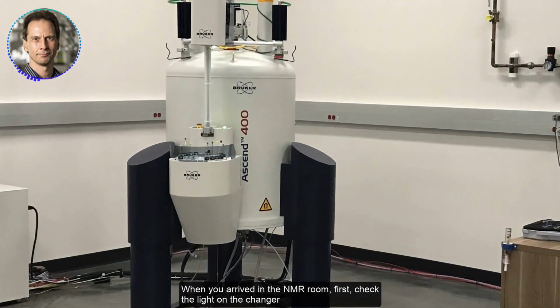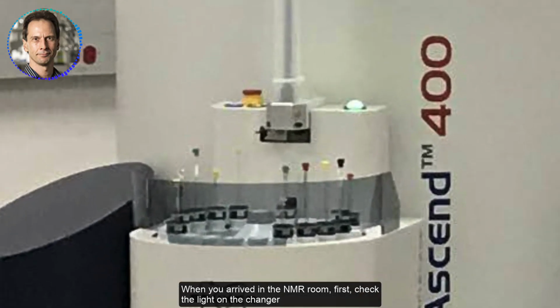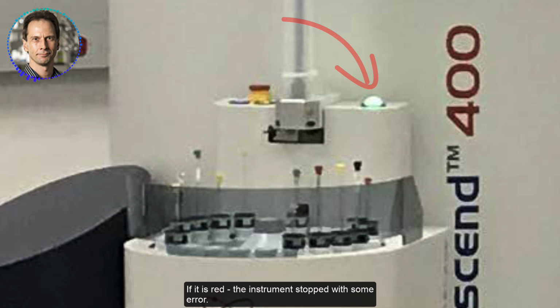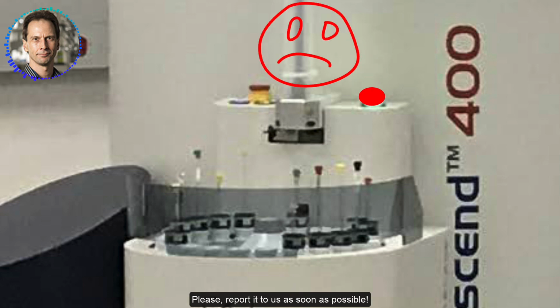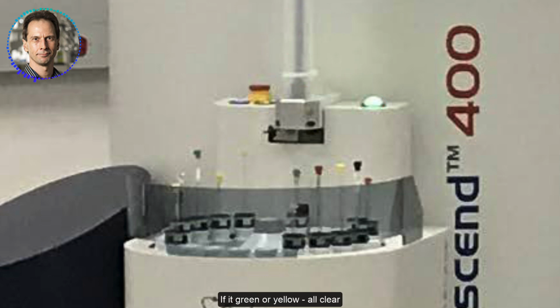When you arrive in the NMR room, first check the light on the changer. If it is red, the instrument stopped with some error. Please report it to us as soon as possible. If it is green or yellow, all clear, you can proceed.